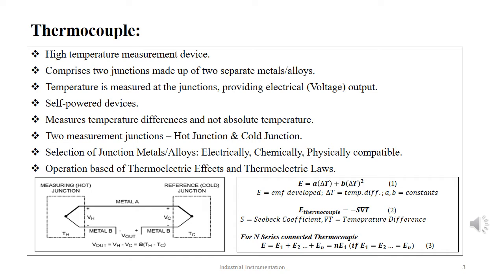The thermocouples work on the thermoelectric effects, that is Seebeck effect, Peltier effect and Thomson effect, and the laws of thermoelectricity, that is law of homogeneous materials, law of intermediate material, and law of successive or intermediate temperature, which are already discussed. There are several types of thermocouples based on the junction, metal, or alloy composition, and each of these types have their own unique features in terms of range, durability, response speed, vibration resistance, chemical resistance, application, and compatibility. The thermocouples can be connected in either series configuration or parallel configuration to form thermopiles.